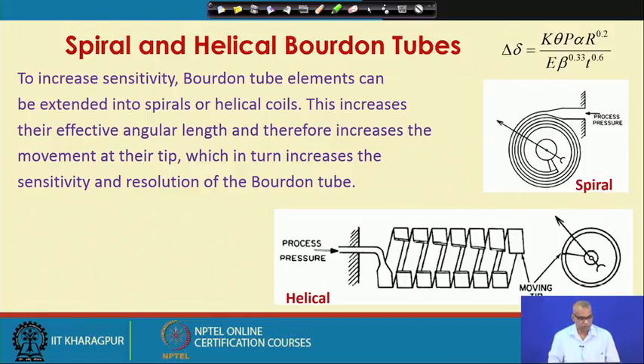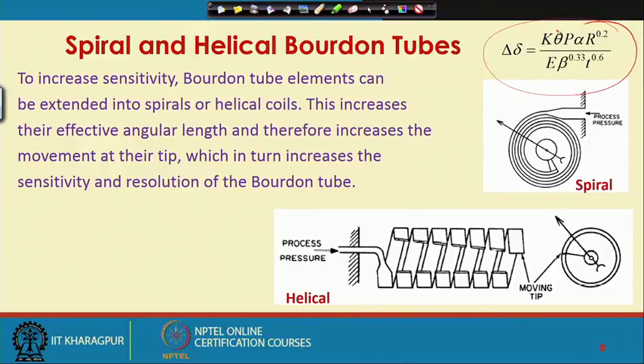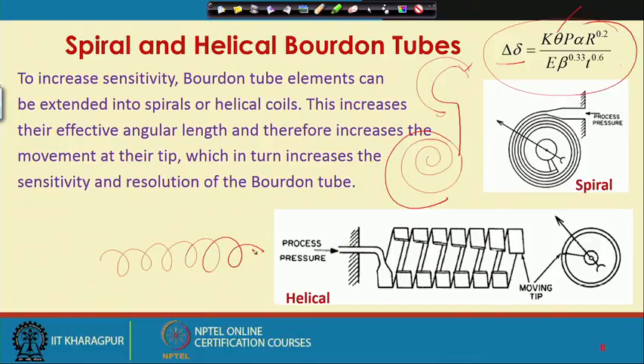Now, to increase the sensitivity of the Bourdon tube elements, what we can do is extend the length of the Bourdon tube. Again look at the equation, which tells you that the tip displacement is directly proportional to the angular length. So, you have this C type Bourdon tube. So, this is the angular length. Now, if you want to increase the angular length further, what I can do is make a spiral Bourdon tube, or I can form a helix structure.